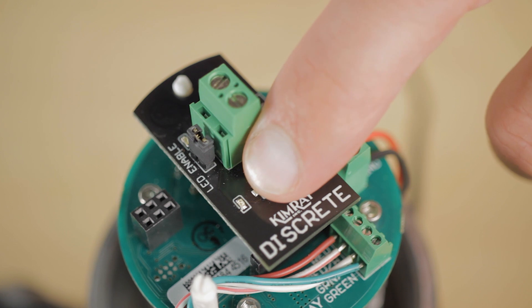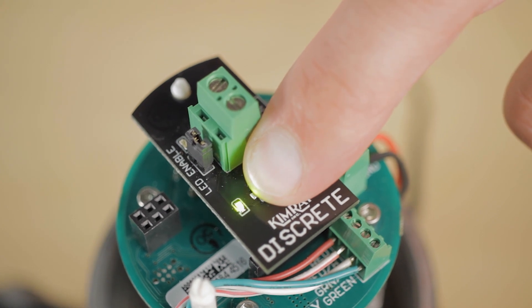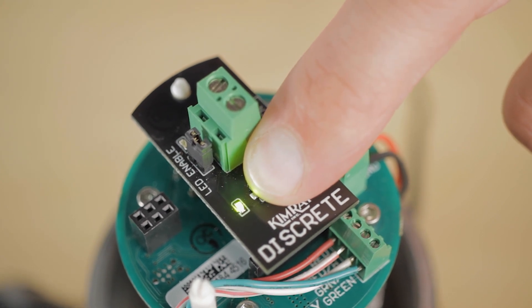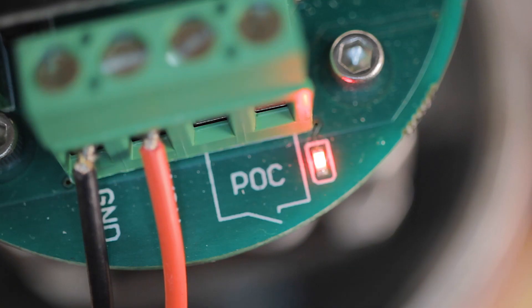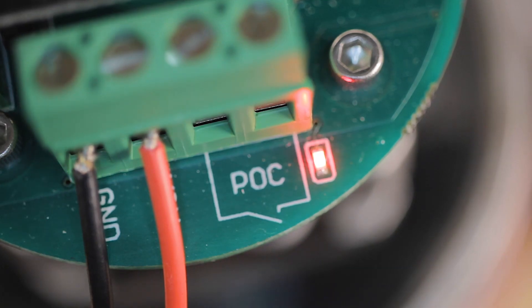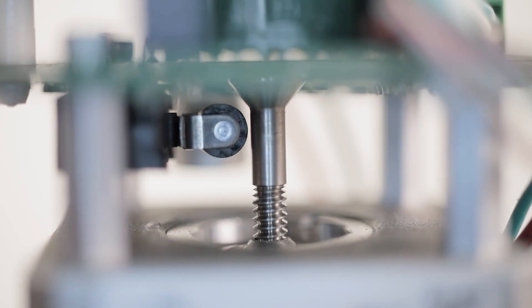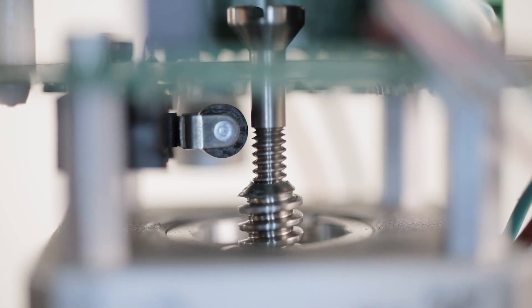We can also test the actuation of the valve with a button for on-off control. There's a green LED when the motor is opening and a red LED when it is closed. It takes about four seconds to fully open and two seconds to close.